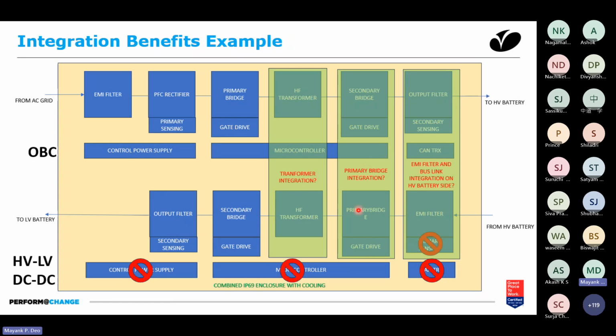So if you look at all these things, they result in significant cost saving. In addition, your PCB becomes combined, and your cooling circuit becomes combined, because typically when the charger is operating, the DC-DC is supplying very limited power. So if you take a 3 kilowatt charger and 1 kilowatt DC-DC housed together, when the charger is supplying to the HV battery, the DC-DC converter is not providing probably more than 200 watts of power, which is very little compared to the charger. So the cooling system needs to be designed for the charger, and the same will be adequate for the DC-DC converter when it is operating on its own and the charger is not operating.